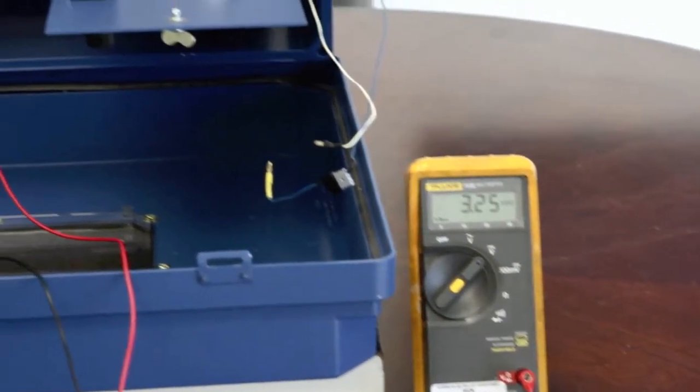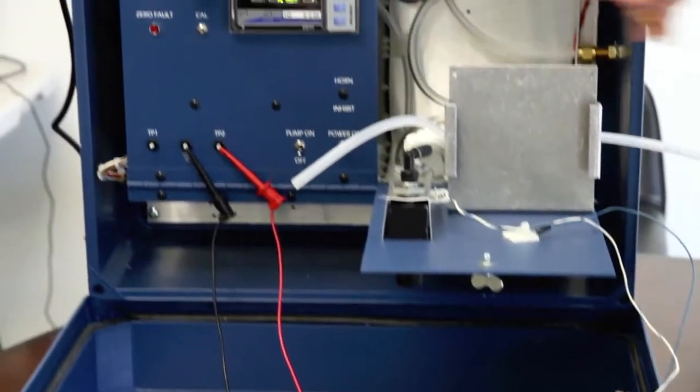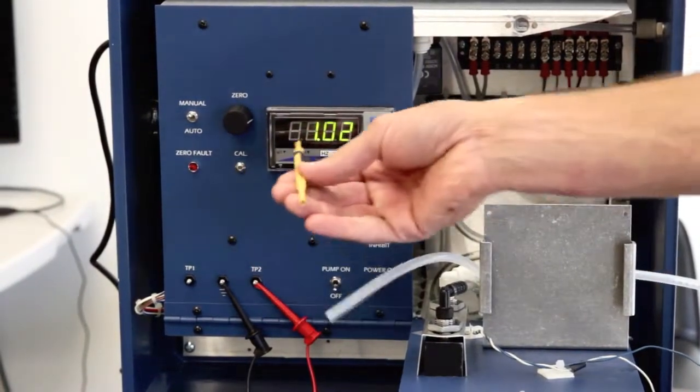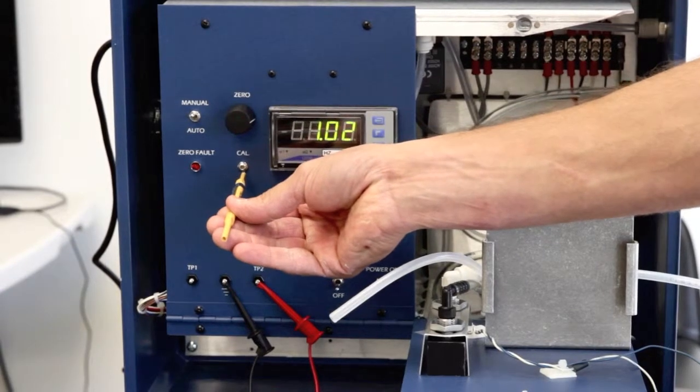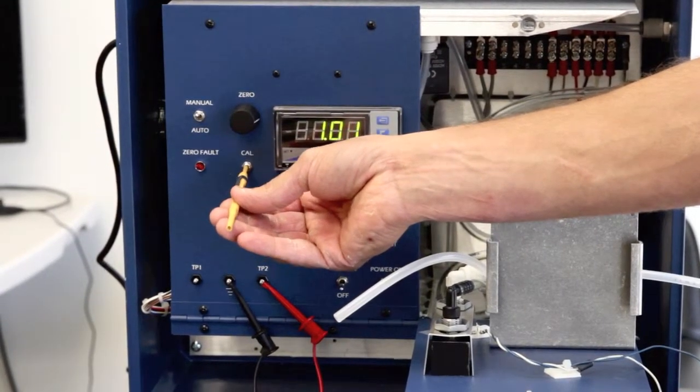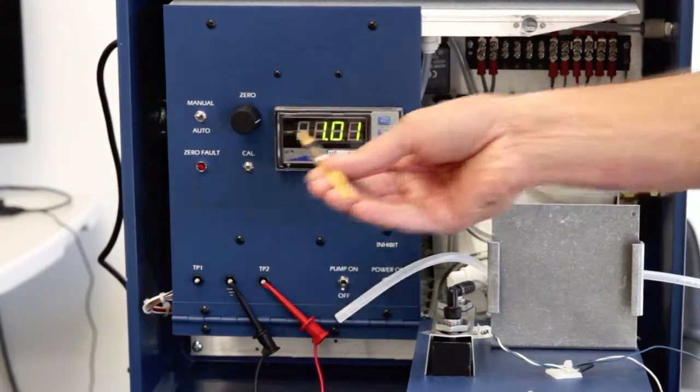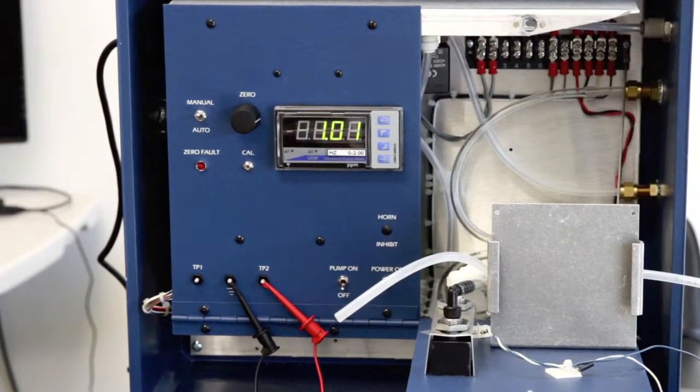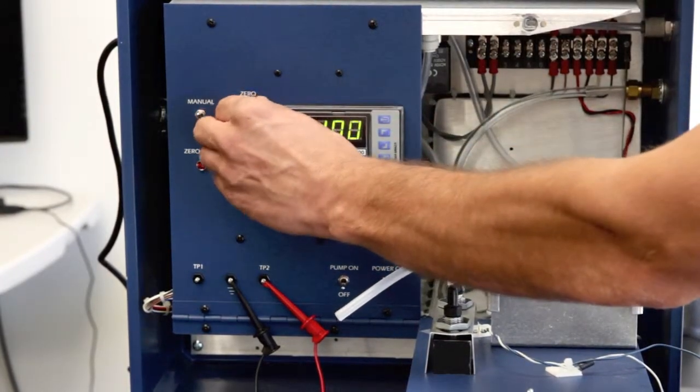Adjust the cal control on the analyzer so that the analyzer display, not the digital voltmeter, reads 1.00. It may take several moments for this reading to stabilize. Re-zero the instrument using the instrument's zero control.